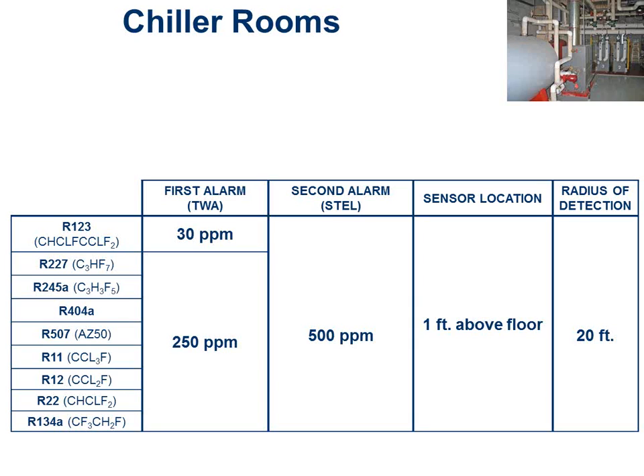And typically we can handle a 20-foot radius of detection, which usually means 1 sensor per chiller. Sometimes I can get away with 1 for 2 chillers if I put it right between them and the chillers are close, but usually 1 per chiller. And for all you fans of a particular brand of chiller, you should just note that not only is R123 on a phase-out schedule, it also has a much lower threshold for safety here. So just keep that in mind. I won't pick on any names because it's an ASHRAE presentation.